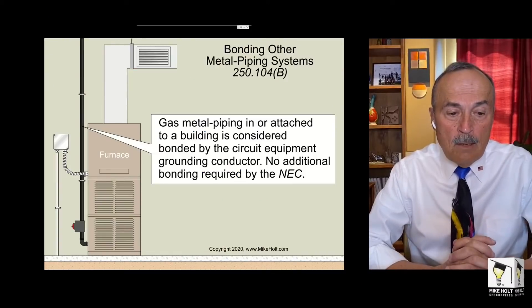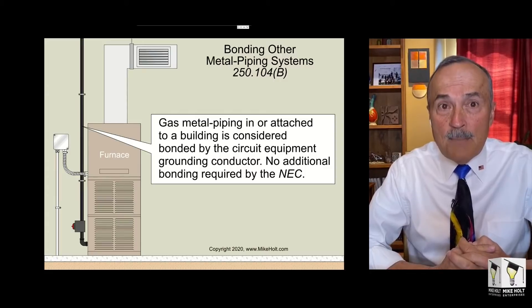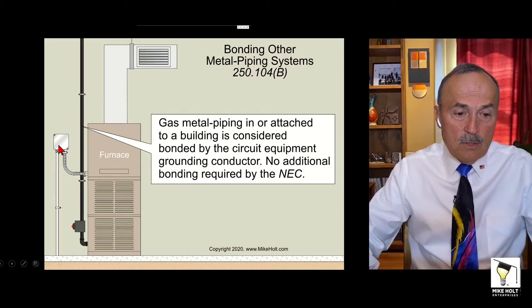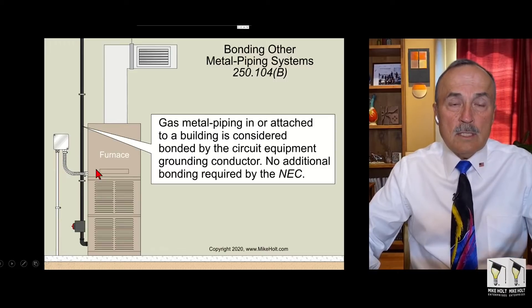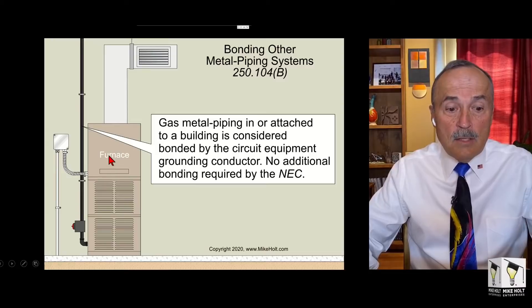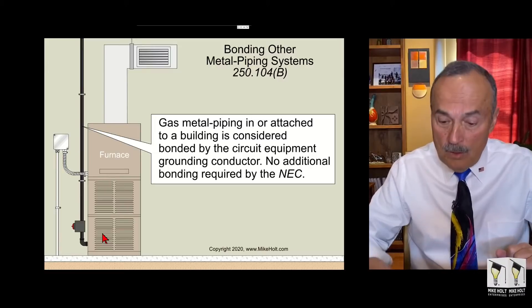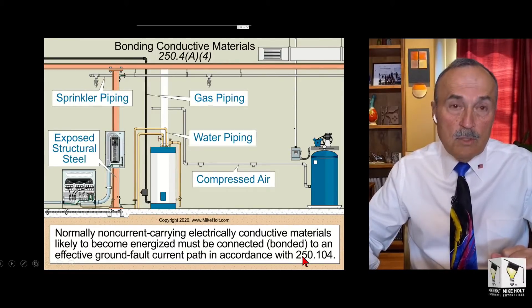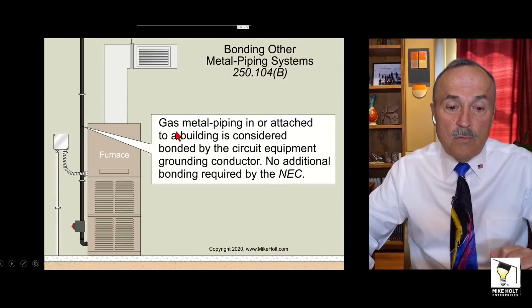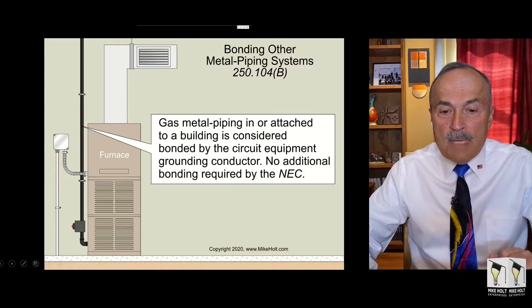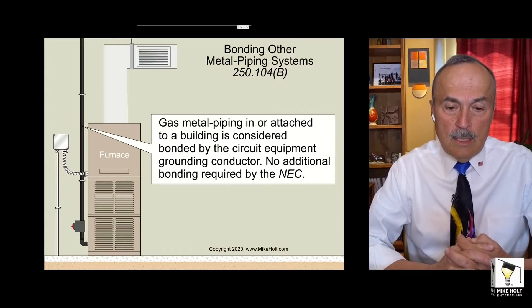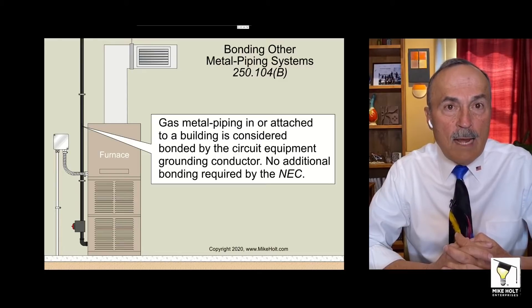The question is often about CSST — corrugated stainless steel tubing — gas piping bonding requirements. In the case of a furnace: you ran an electrical circuit to the furnace, so the non-current-carrying conductive parts of that metal furnace are likely to become energized. Per 250.104(B), gas metal piping in or attached to a building is considered bonded by the circuit equipment grounding conductor.